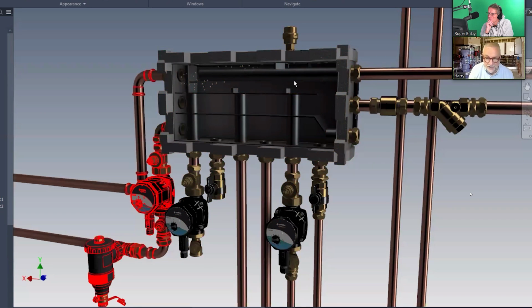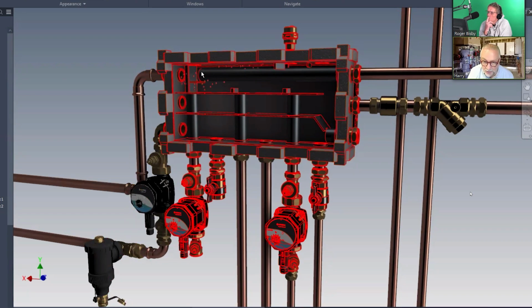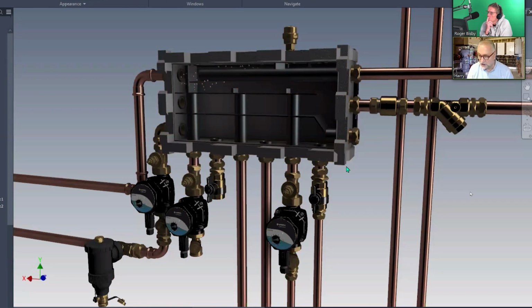But if I change it around and I put a heat pump in from this side, the heat pump can come through this pipe, ends up in the exact same place, hits this V-shaped baffle, turns back on itself and goes the exact same path and back to the boiler here. So the complications are gone. All these things of close couple T's and trying to figure out how do you bypass valves and how do you protect the heat pump from being obstructed by controls, or where a guy doesn't fully understand what he's doing.